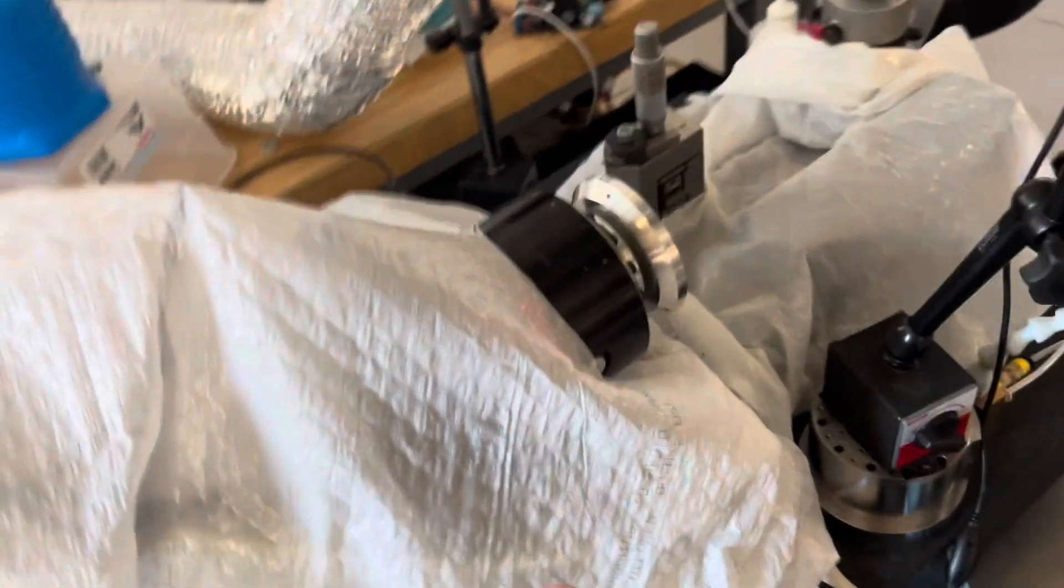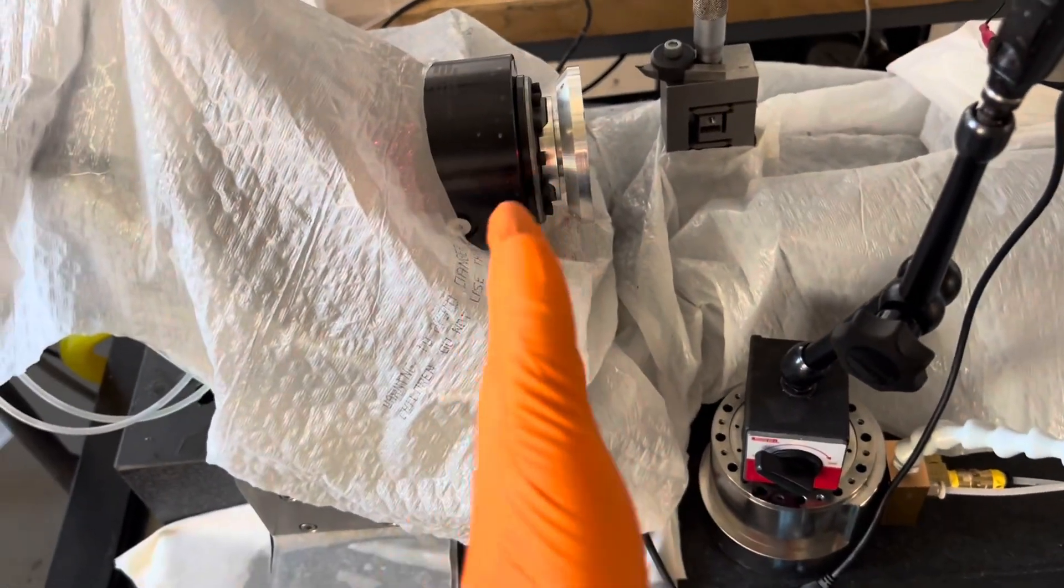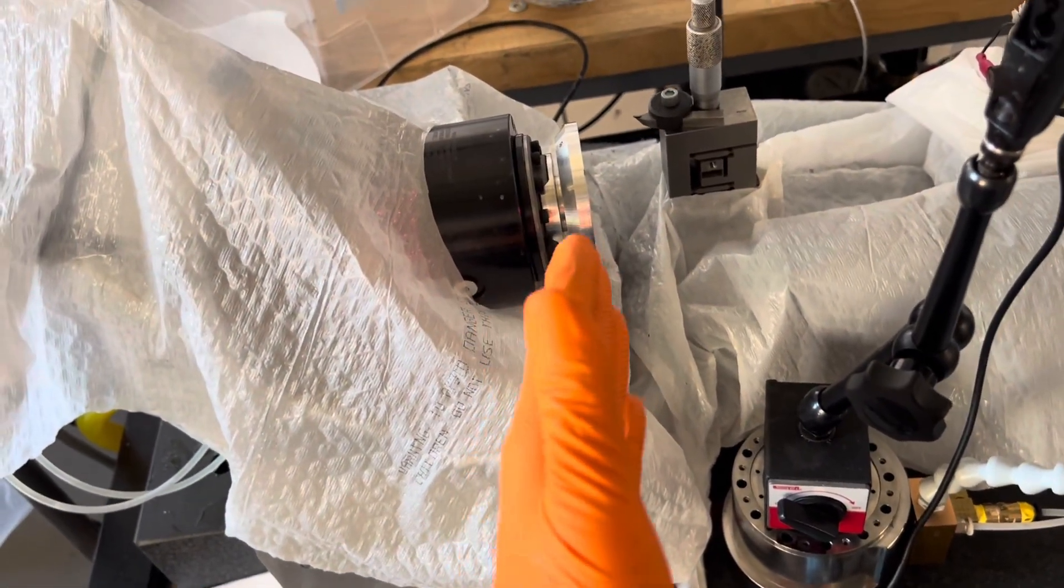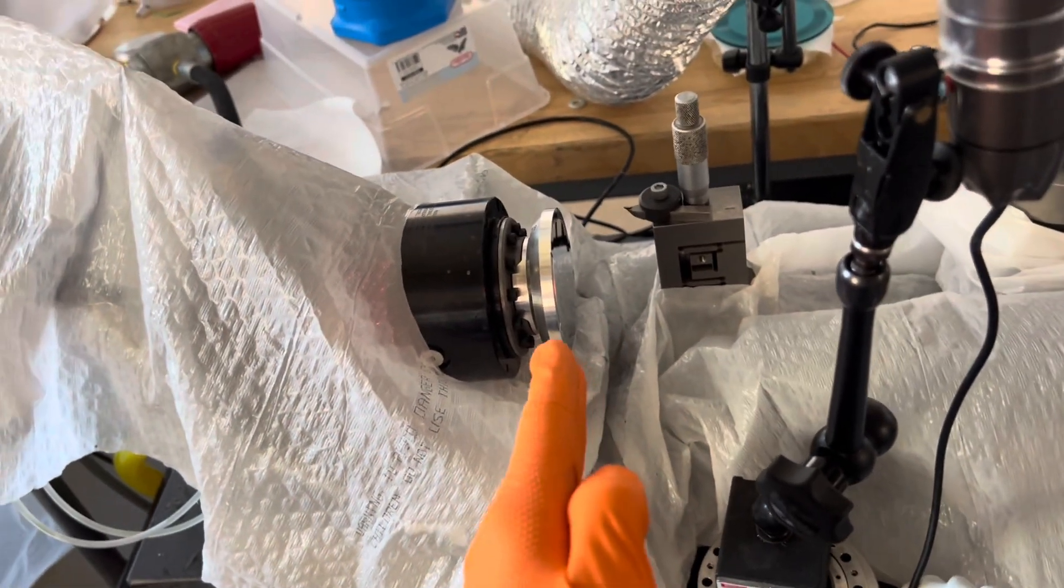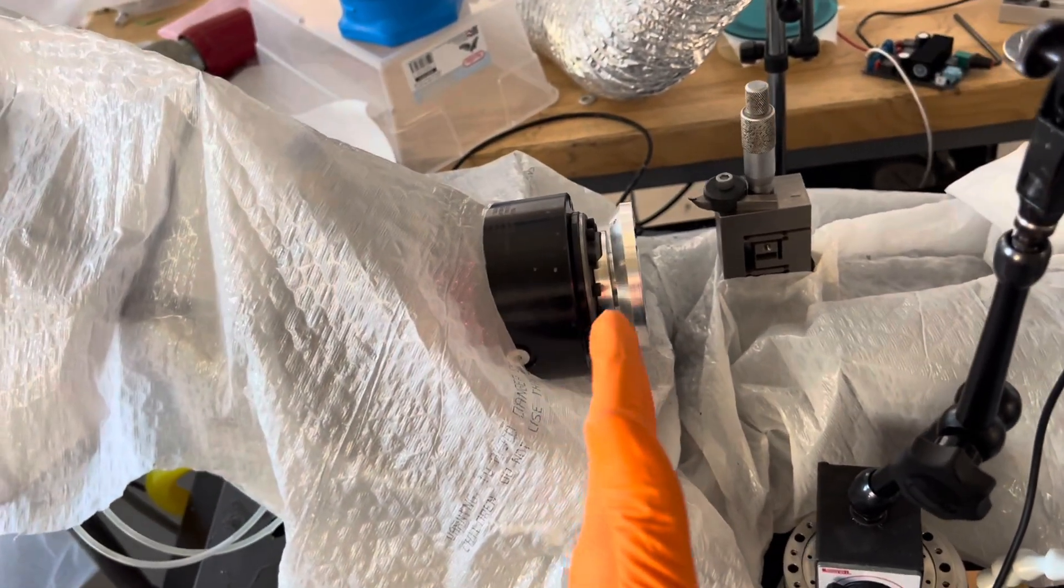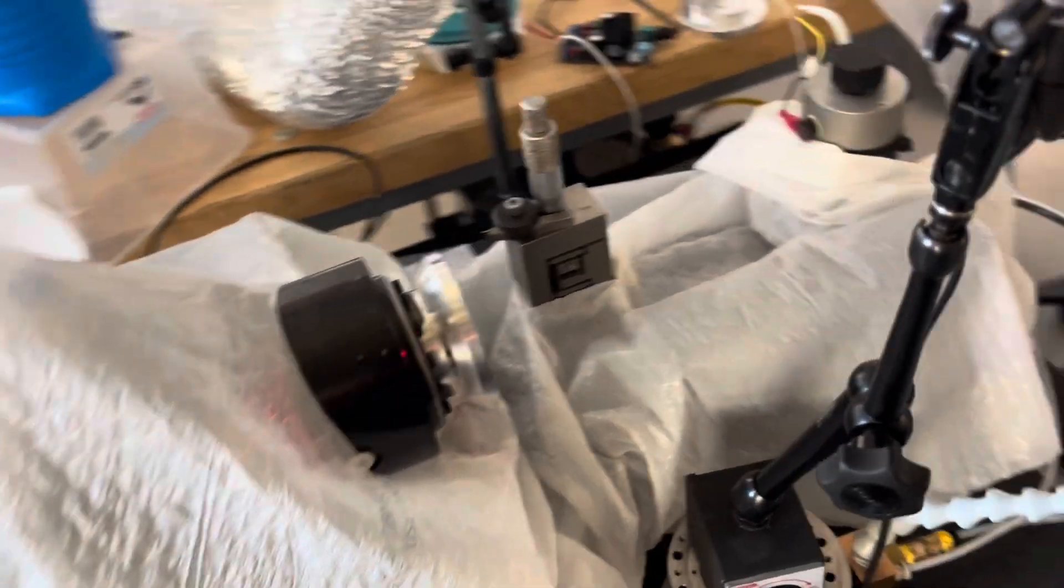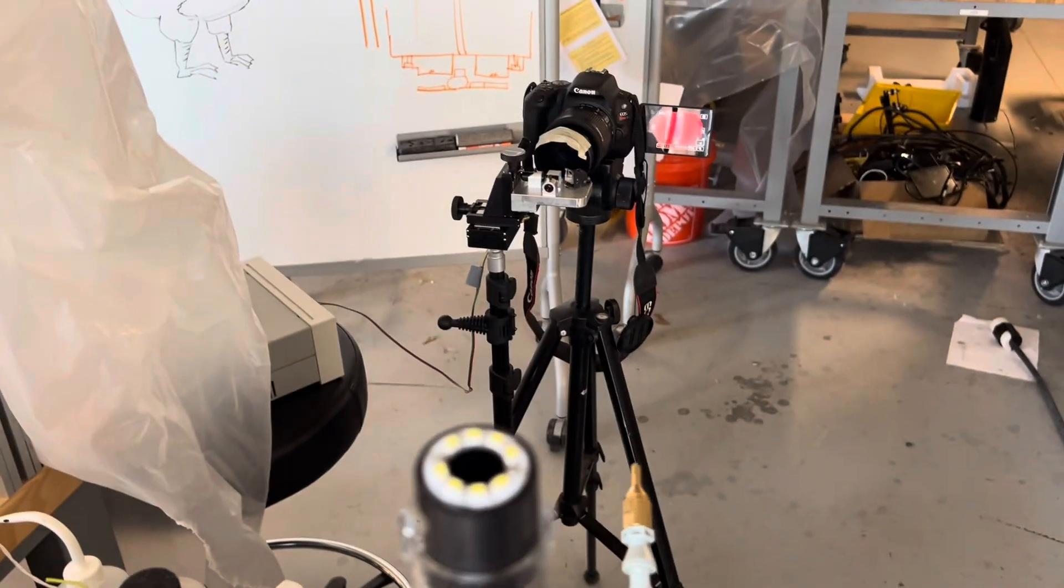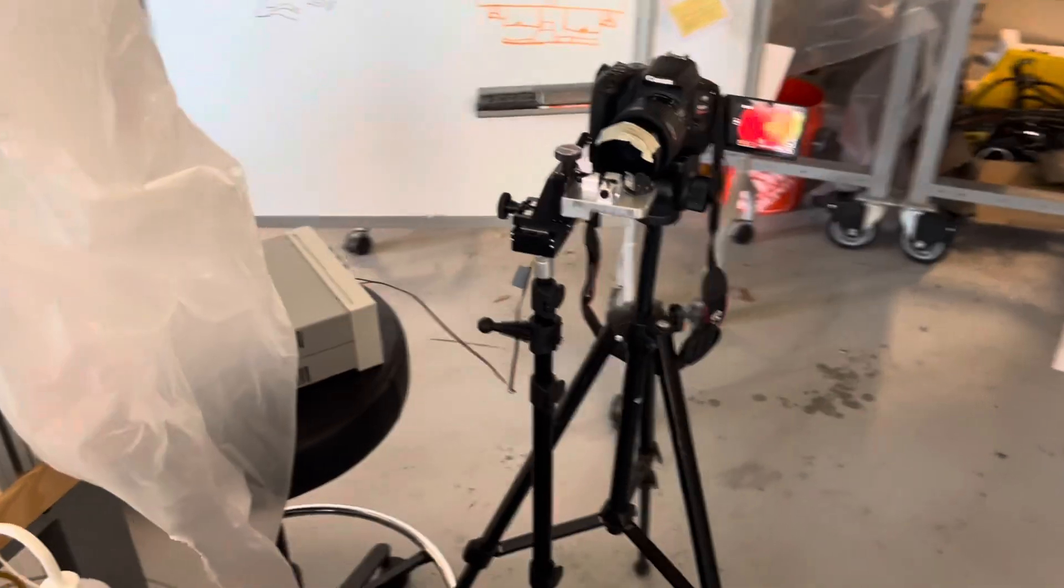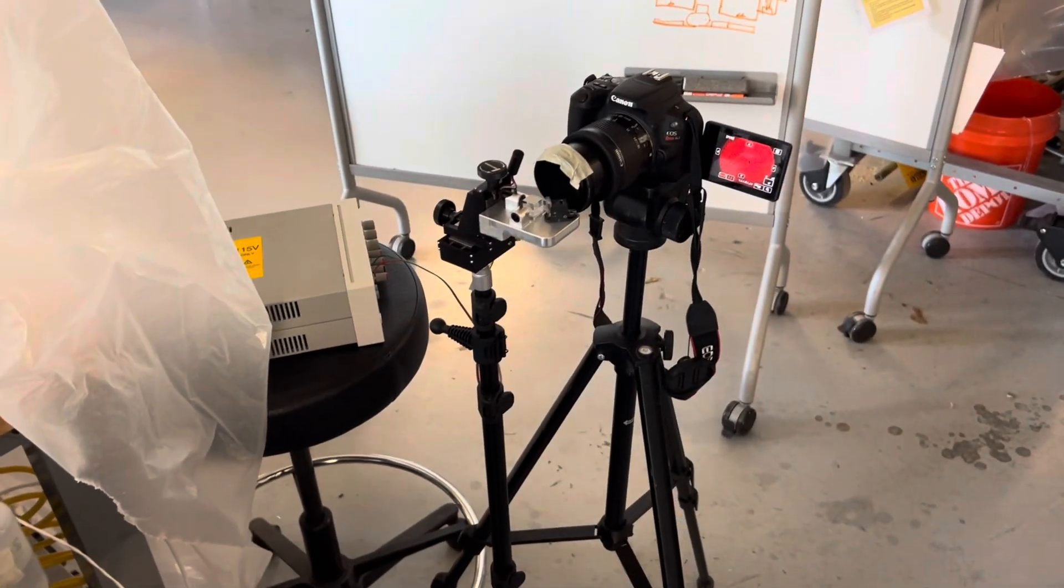And because of the repeatability of the coupling, the tilt is not appreciably changing every time you rotate it because the optic face is very well aligned and perpendicular with the spindle axis. So besides the whole pain in the butt alignment, this is a pretty nice setup.